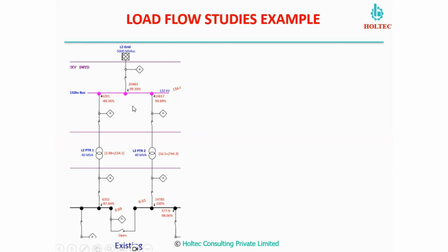But what is happening? This power factor in this area is okay, but here it is actually on leading condition. So what is happening? The result of this leading power factor is the increase in the voltage, distribution voltage of that particular bus. So you know when the voltage will increase, your fixed losses will increase, and this is also not advisable to operate the plant with leading power factor at any of the buses.